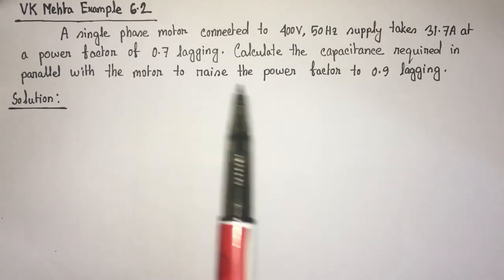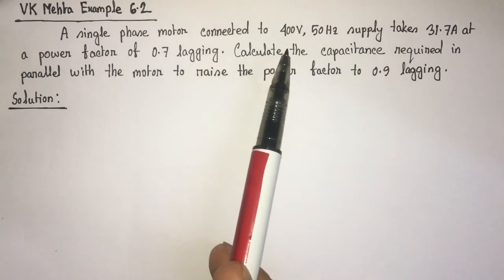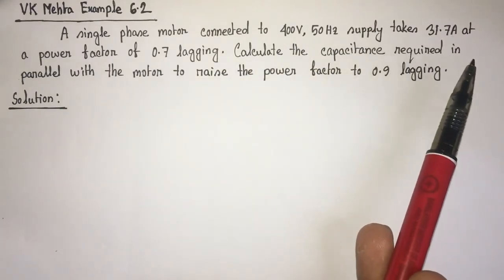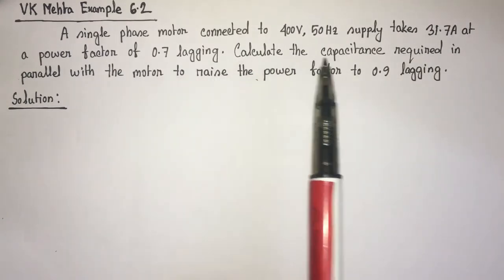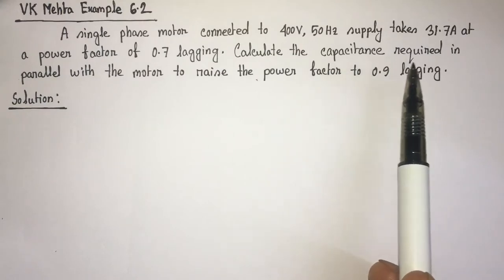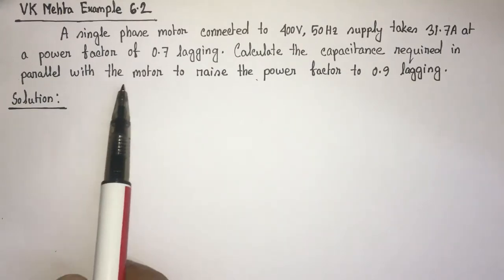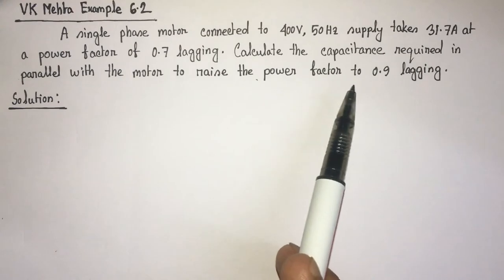Here, a single-phase motor is connected to a 400V, 50Hz supply and takes 31.7A current at a power factor of 0.7 lagging. We have to identify the value of capacitance required in parallel with the motor to raise the power factor to 0.9 lagging.